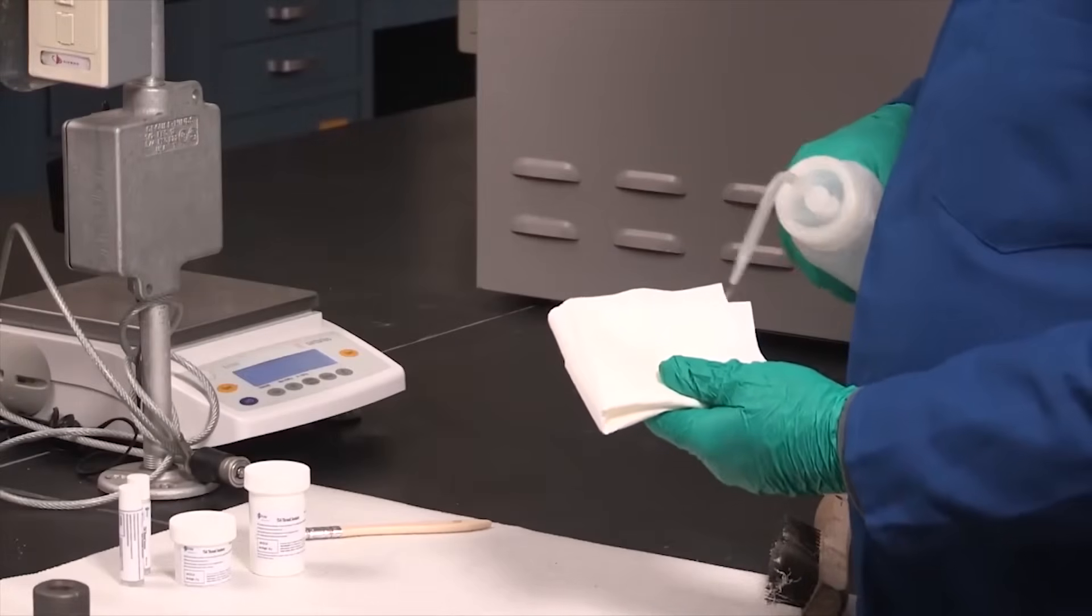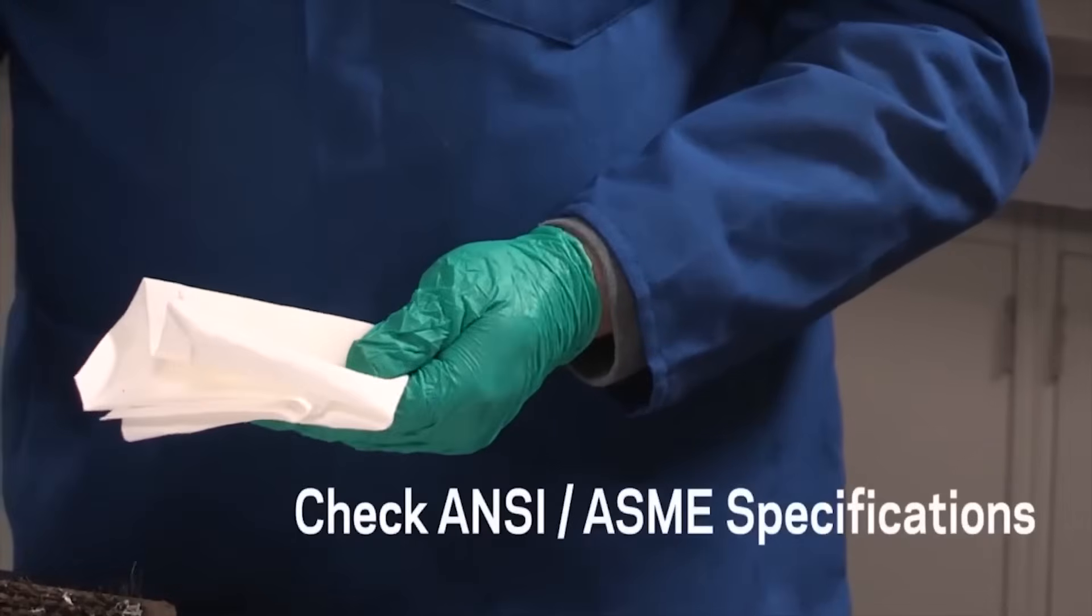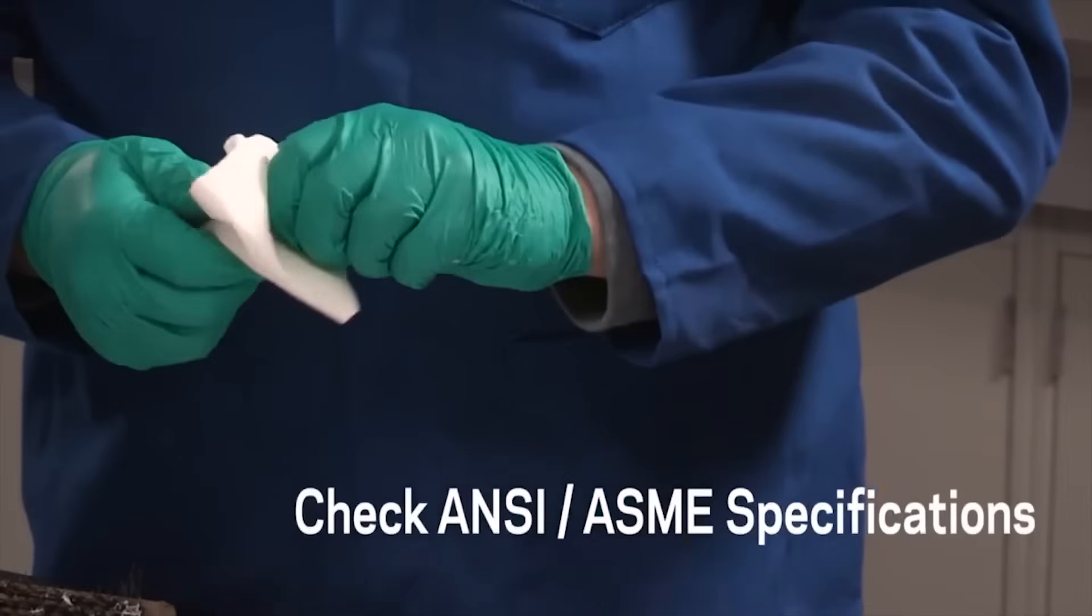Clean all pipe and fitting threads with a non-chlorinated solvent to remove any cutting or protective oil, and chase the threads with a stiff wire brush to remove burrs, debris, and old sealant such as PTFE tape, pipe dope, and anaerobic resin.